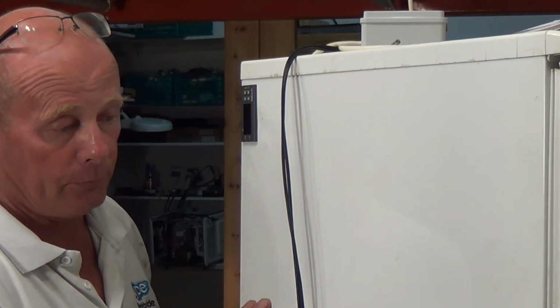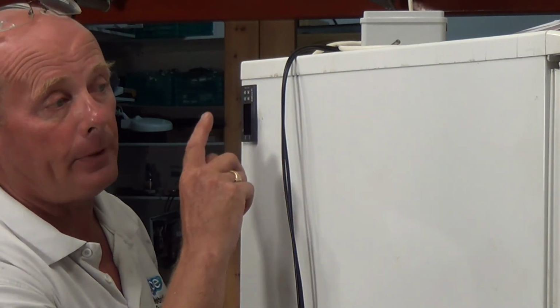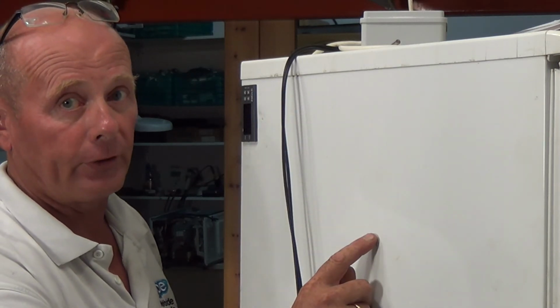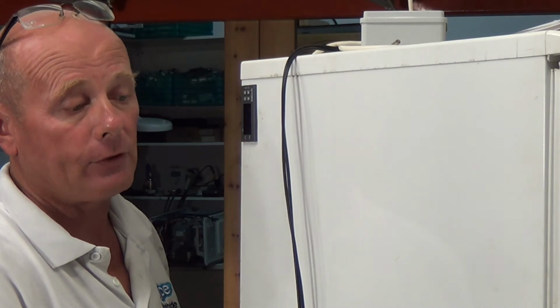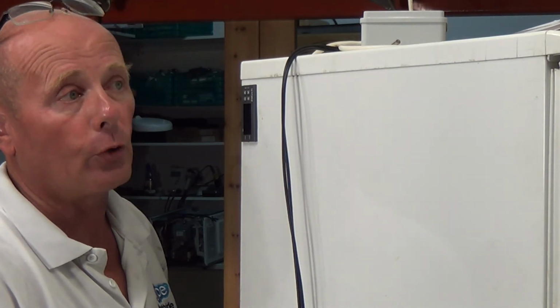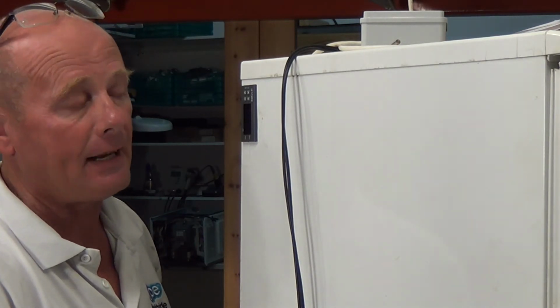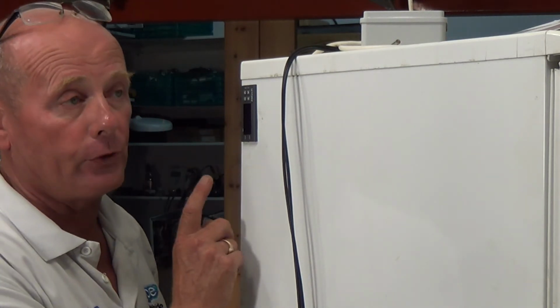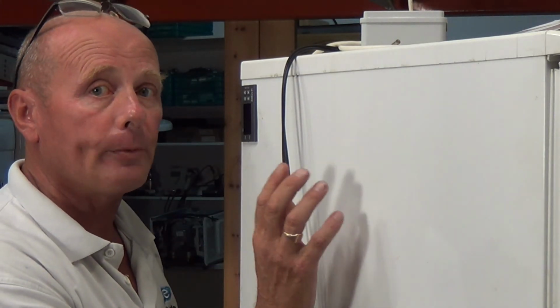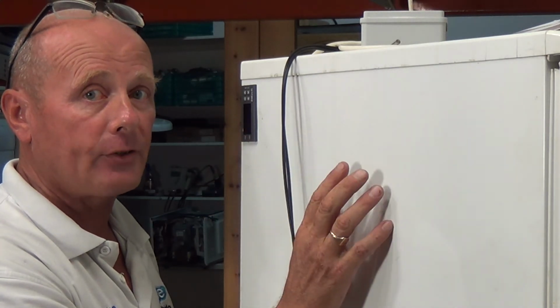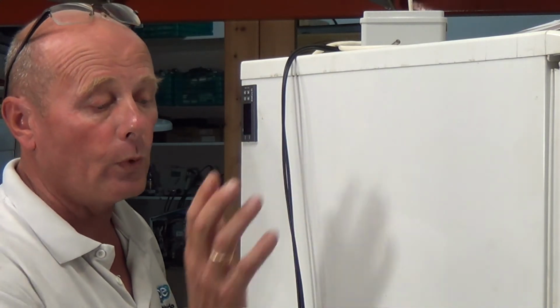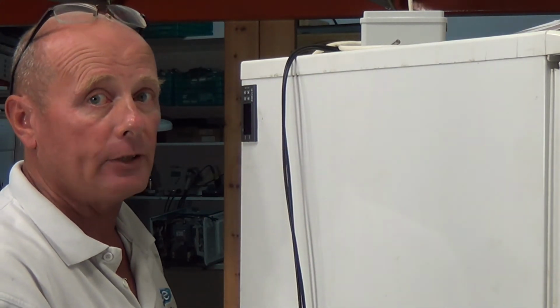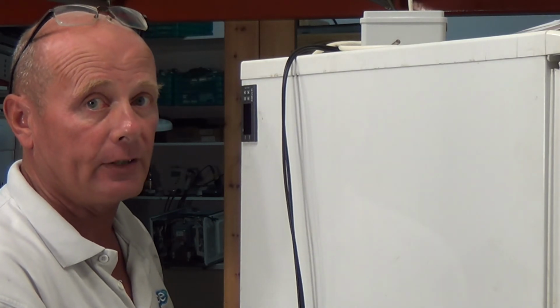This is a single compressor. The gas comes up through the freezer first and then starts cooling the fridge after. So we've got our sensor in the fridge, so we are going to be monitoring the temperature with the thermostat from the fridge, which should give us an automatic temperature of about -16 in the freezer, with an air temperature of somewhere in the region of 4 or 5 degrees in the fridge.